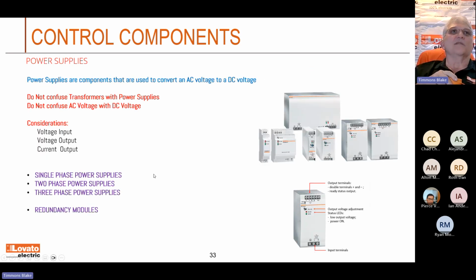Now let's look at the power supplies. Power supplies got a little more involved in it. This is where we're taking AC voltage and turning it into DC voltage. And they used to do it real simple with just a bridge rectifier and some capacitors and maybe a voltage regulator on the output. But nowadays they modulate that thing. They take that waveform and modulate it up around 100 kilohertz.